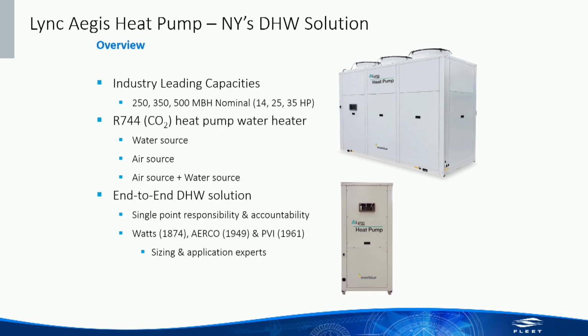The other thing to consider when you're talking about domestic hot water and heat pumps is certainly an end-to-end solution. On the HVAC side, contractors, engineers, operators are more used to working with heat pumps and refrigeration systems. When you get into the plumbing world, it's a completely new technology. It's a completely understaffed, undereducated community that has never really had to deal with heat pumps or refrigeration circuits in the past.